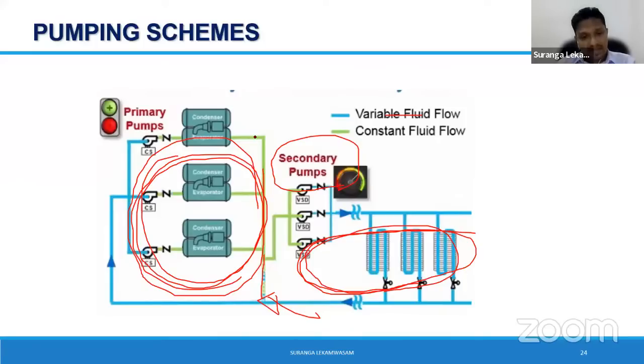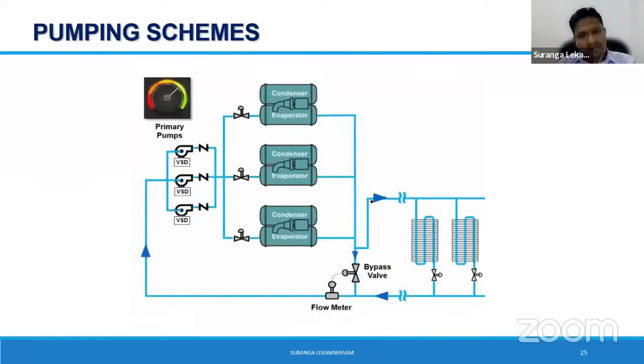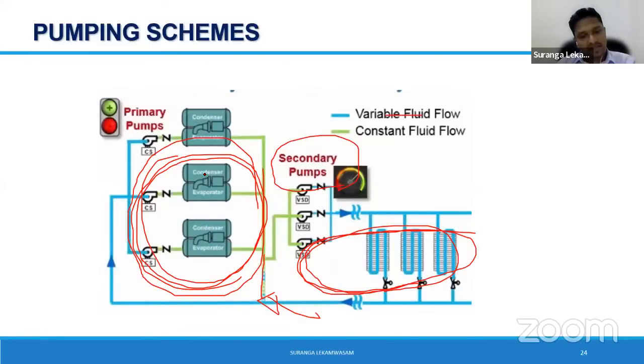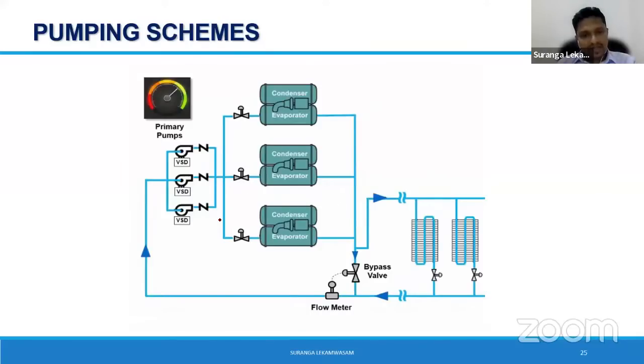There may be many more reasons, but that is one of the key reasons they were not willing to reduce the flow rate through the chiller. But nowadays, with modern controllers and advancements, they say you can reduce the flow rate up to maybe 50%, right? Therefore I don't need this primary set of pumps, because that is a waste of energy. Since it is a constant flow rate irrespective of my load side, it is a wastage. So I can eliminate all these primary pumps and use a single set of variable speed pumps to run the load as well as run through the chillers, because I can unload the flow rate even through the chiller, probably up to 50%, right?